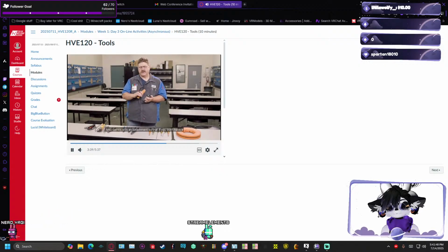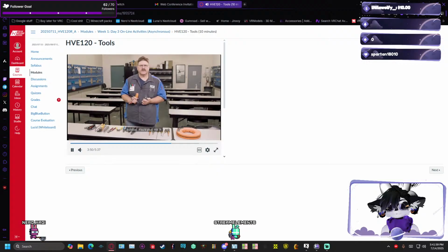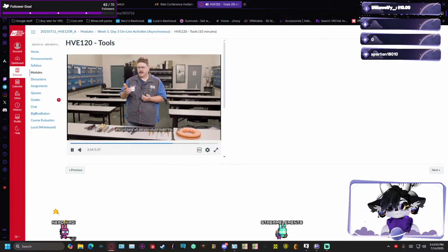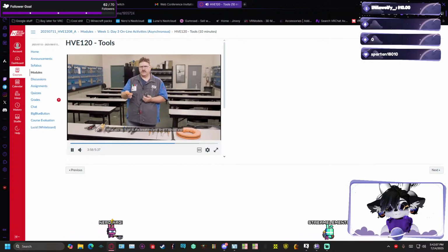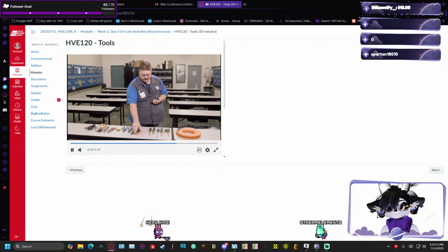It also comes with an attachment so that if you don't have a receptacle, you just have conductors. Let's say you're in a junction box in an attic, and you need to identify what circuit that is so that you can turn it off without turning off other parts of the building. You'd plug this in, it sends a frequency back on the conductors, and this unit here will tell you what breaker it is. All you do is go to the breakers and tone it across, and it'll make that sound when it finds the correct breaker.